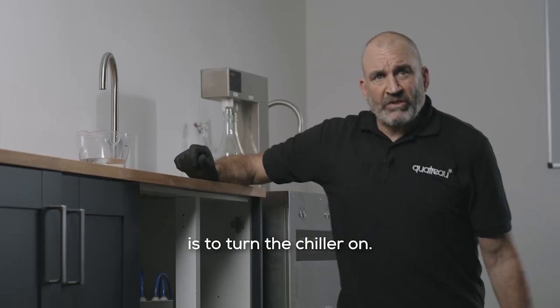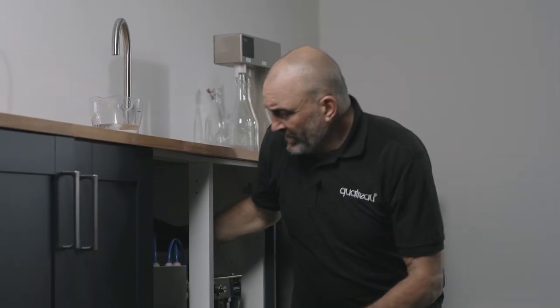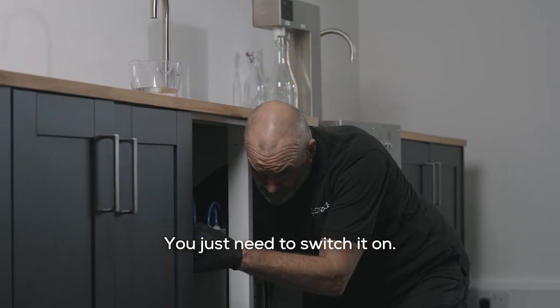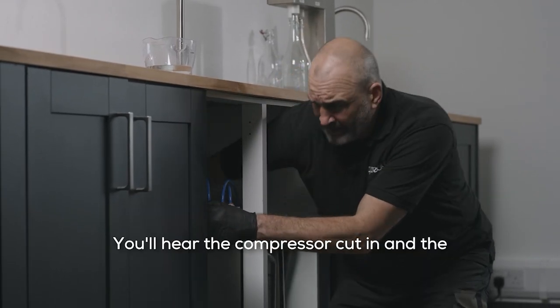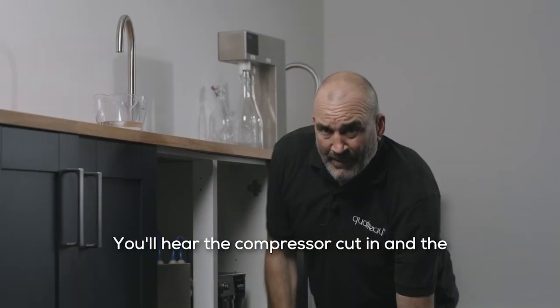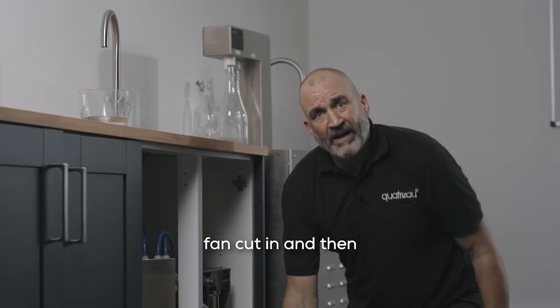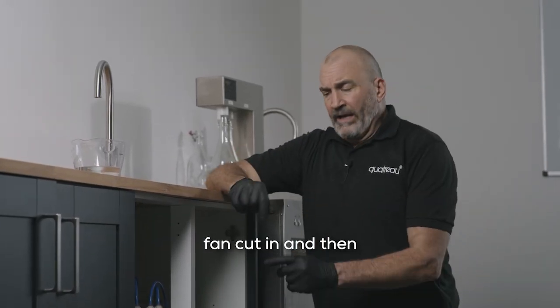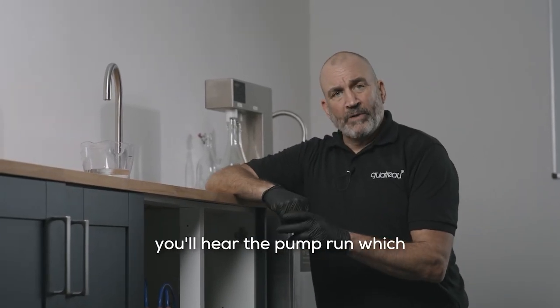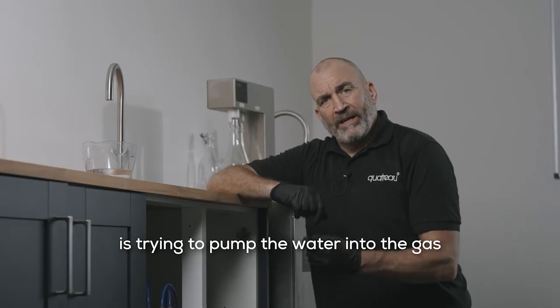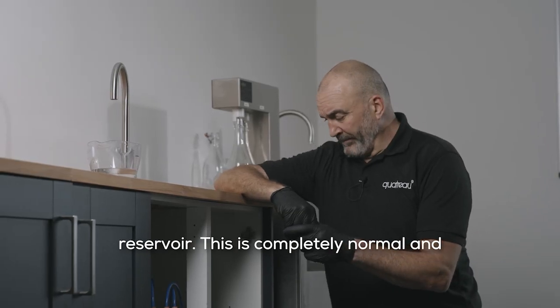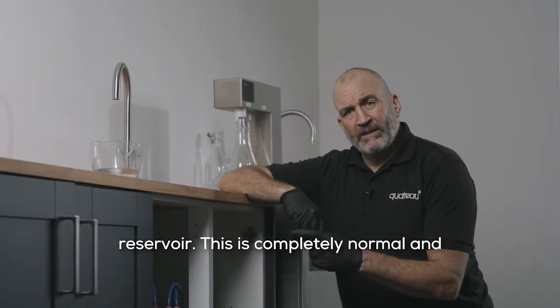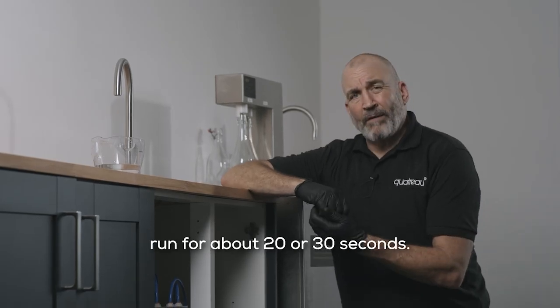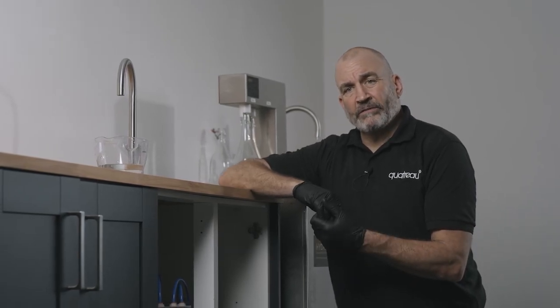The next stage is to turn the chiller on. You just need to switch it on. You'll hear the compressor cut in and the fan cut in. And then you'll hear the pump run, which is trying to pump the water into the gas reservoir. This is completely normal. And the pump should just run for about 20 or 30 seconds.